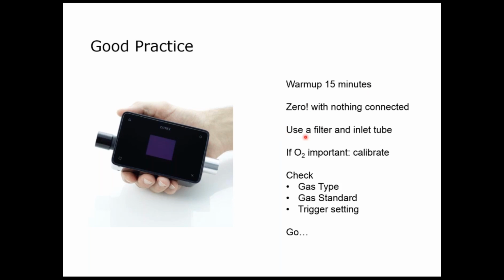Then I will show you how to use the filter and the inlet tube. I will show you how to calibrate the oxygen sensor. The oxygen sensor does not need to be calibrated before every measurement, unlike the zero, which should be done before every measurement. But the oxygen should be done once a week or before important oxygen measurements. Then we will check the gas type, gas standard, and trigger settings before we do our actual measurement. So let's see how this works in practice.